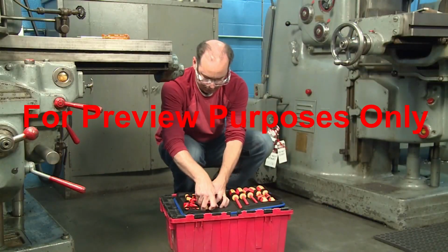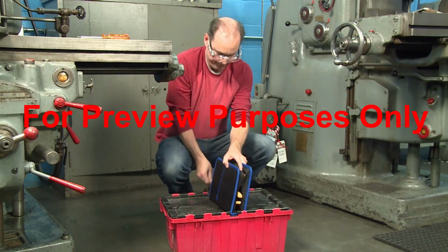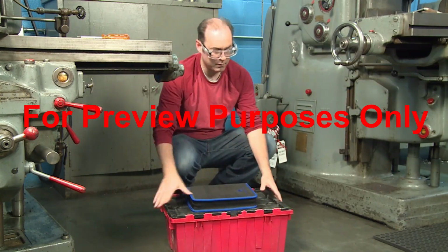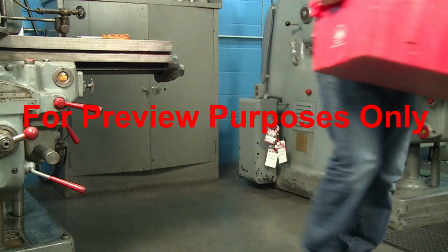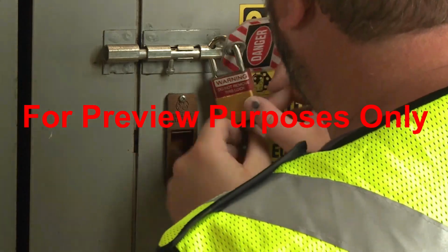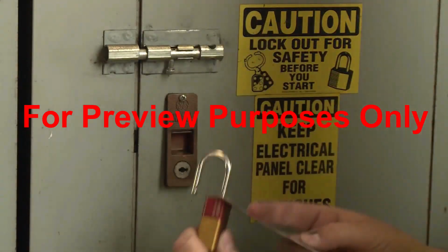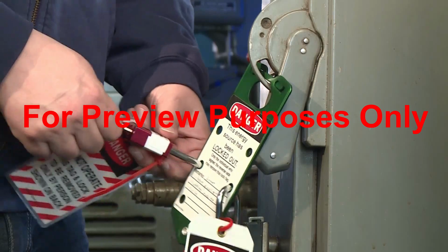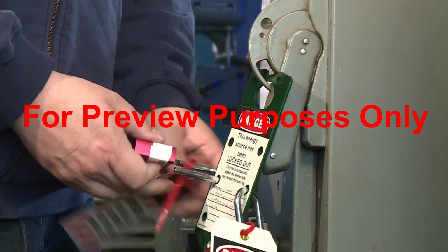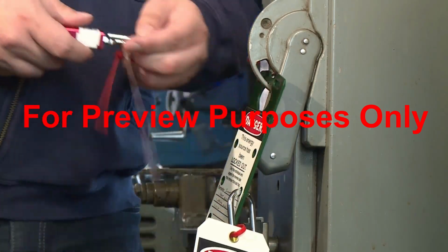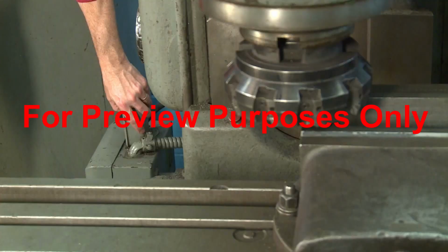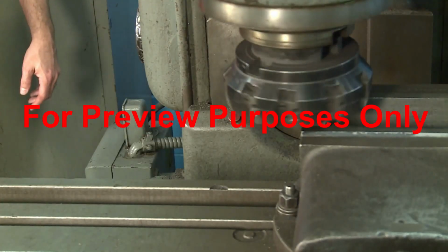At this point, the maintenance or other service tasks can be performed safely. When the work on the equipment is complete and all workers are physically clear of the equipment, the qualified person will determine if it's safe to restore power. Tags and locks can then be removed. When multiple locks have been used, each of them must be unlocked by the person who originally applied them. The power can then be turned back on.